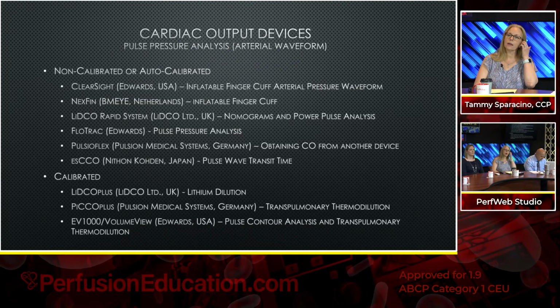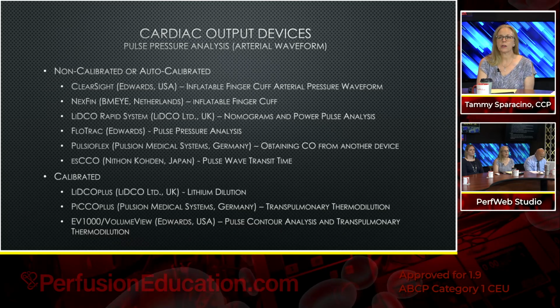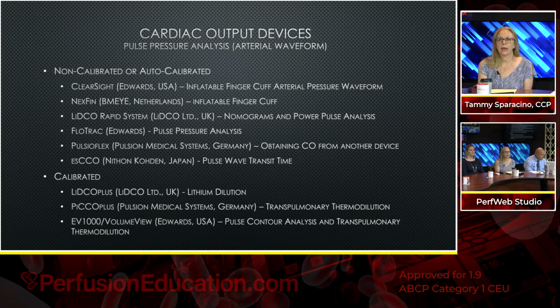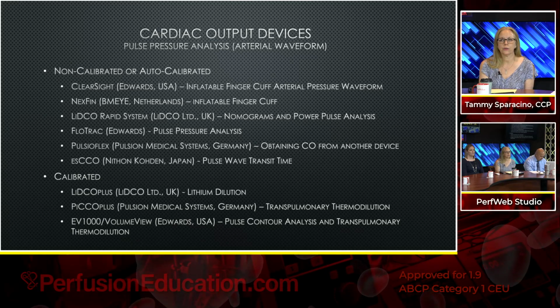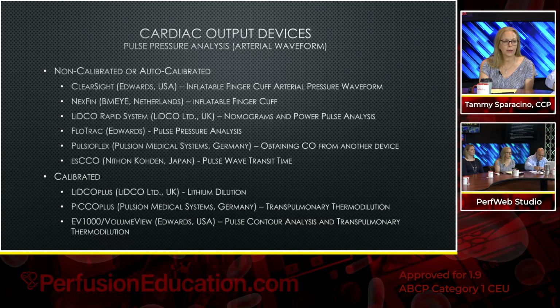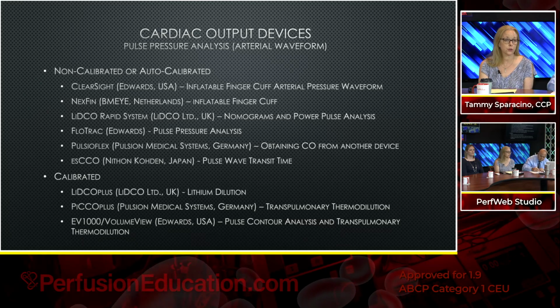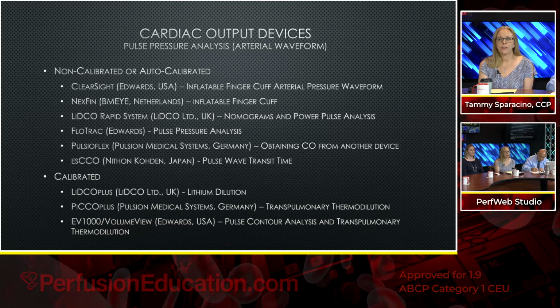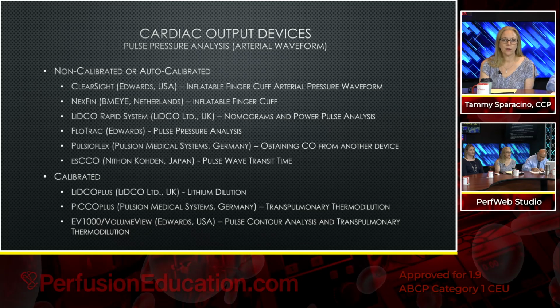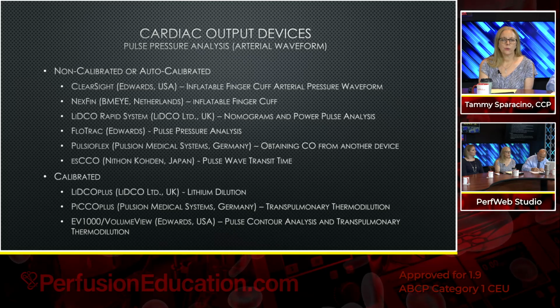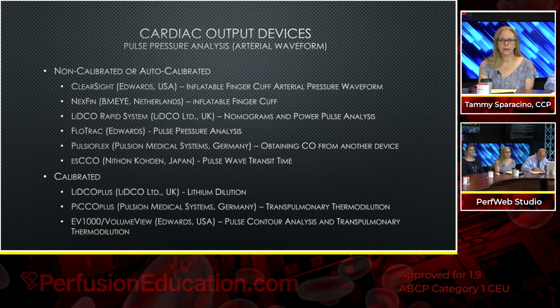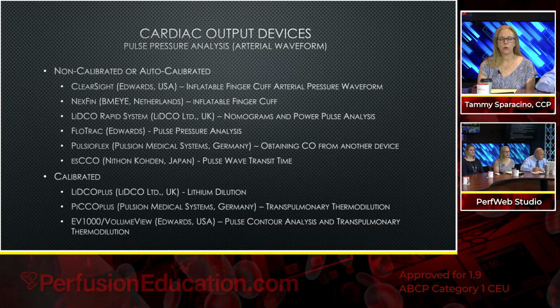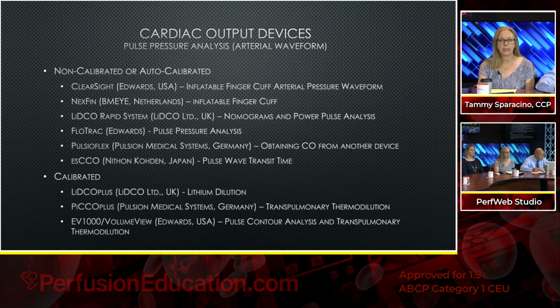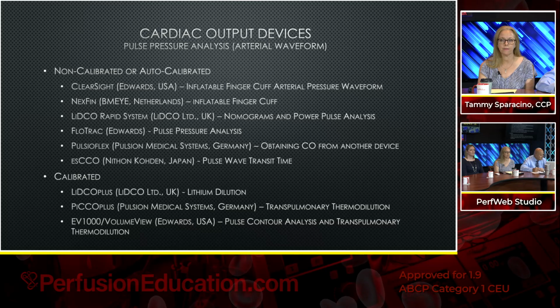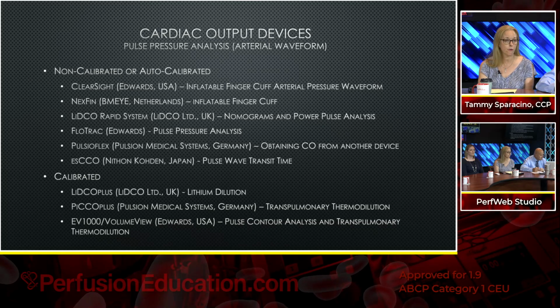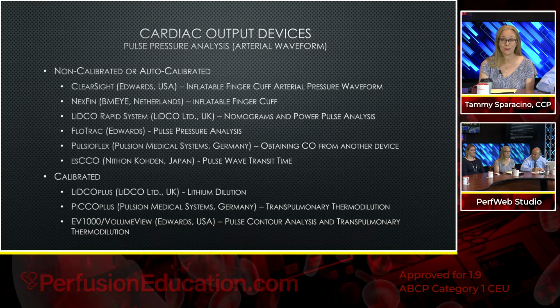Okay, so let's talk about the one that seems to be the most common, especially in cardiac. We're talking about technologies that use pulse pressure analysis, relying on the arterial waveform to get their derived parameters. So we've got the non-calibrated, or some of them are also auto-calibrated. There's one called ClearSight, and this is from Edwards. The device is an inflatable finger cuff. From that finger cuff, it gets the arterial pressure waveform, and that's how it derives all of its parameters.